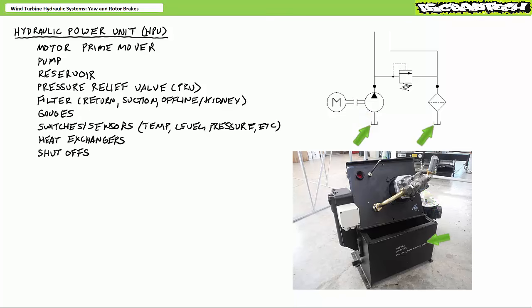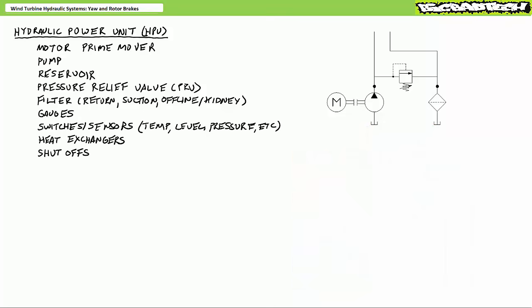The reservoir's principal purpose is to store fluid not in use and ensure the pump has a ready supply of oil available when required. Additionally, the reservoir serves to clean and cool oil before it's pumped back into the system. Additionally, most hydraulic power units include a pressure relief valve and a means of filtration, since they're essential to the safe and efficient operation of the larger system.